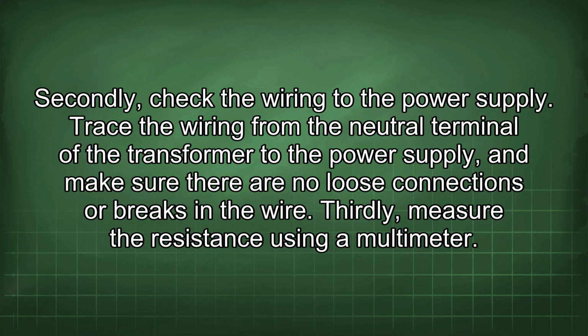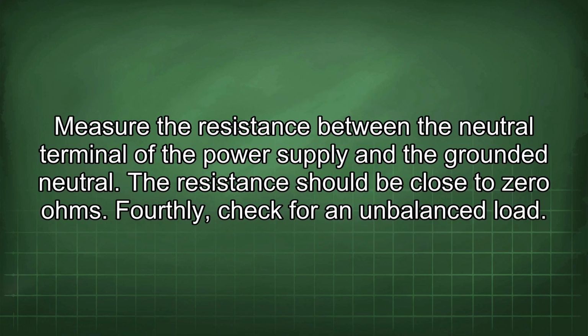Thirdly, measure the resistance using a multimeter. Measure the resistance between the neutral terminal of the power supply and the grounded neutral. The resistance should be close to 0 ohms.